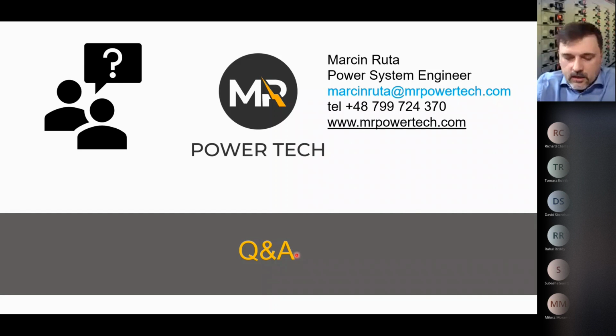And I can add one point. You need to prove that. So for example, if you switch off things, then you have to measure. And for measuring, you need to have PPE, because we still consider this live equipment. So you might as well have PPE for switching off and then measuring. So I hope this explains your question. As a rule of thumb, just having IEC doesn't mean that it's safe from an arc flash point of view.